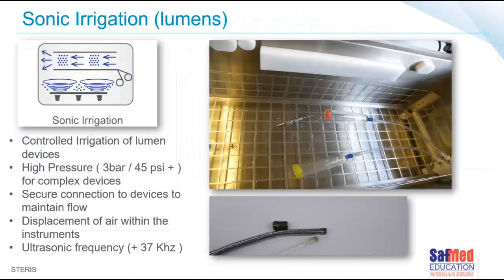So here's an image of a fine suction, and it's connected to the lumen of the sonic irrigator using a connector. This type of ultrasonic, as we said, will clean not only the outside of the device, but also flush with sonics down the lumen. Each make and model will specify the ultrasonic frequency as well as the actual pressure for flushing, but it can be at around 3 bar. Of course, very important to use the right size attachment so that you can secure the attachment correctly to the device being washed.